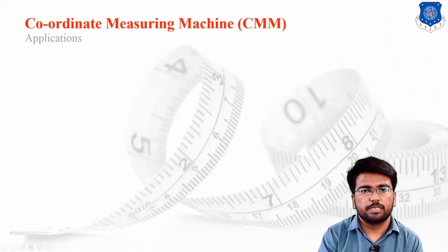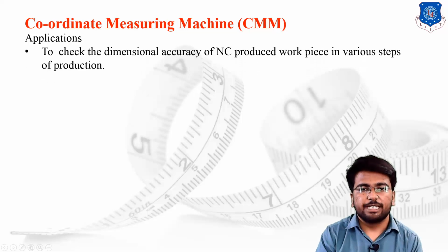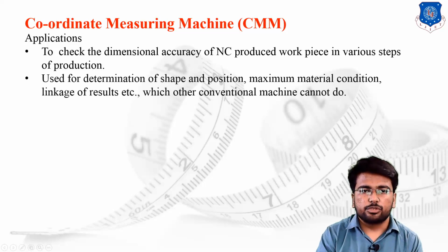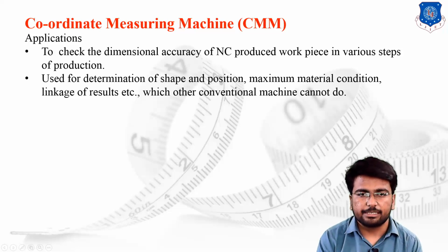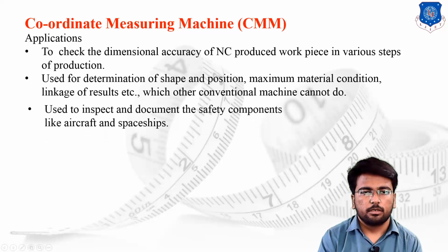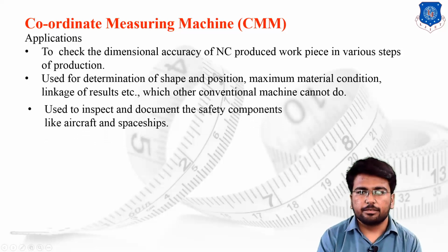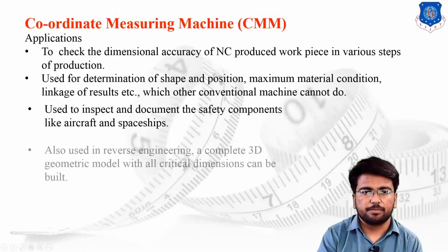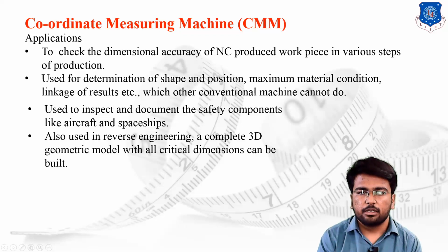Now, the last topic of the CMM is the applications. The CMM is very useful to check the dimensional accuracy of all NC, numerically controlled, produced workpieces in the various steps of production, used for determination of shape and position, maximum material condition, then linkage of the results, etc., which other conventional instruments cannot do simultaneously. It is used to inspect and document safety components like aircraft and spaceships. Also, it is used in reverse engineering. A complete 3D geometric model with all the critical dimensions can be built by using the CMM.